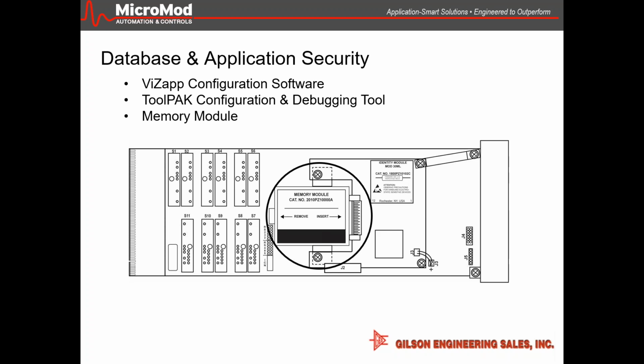It measures about 3 inches by 2.5 inches by an inch, and it takes a snapshot of the database every 50 milliseconds. So if you leave it in read-write mode, it will maintain a memory, a snapshot if you will, of everything in that controller. Even if you made a change to your characterization table, a tuning parameter, or an alarm point a minute ago, and then the controller failed, you could remove that memory module, put it into a new controller, and slide it into the housing. The module will go back to its last good checksum, and that's what it'll load into the controller. When you slide it in, it says upload, you say yes, and you're off and running. It takes about 10 seconds once it initializes.